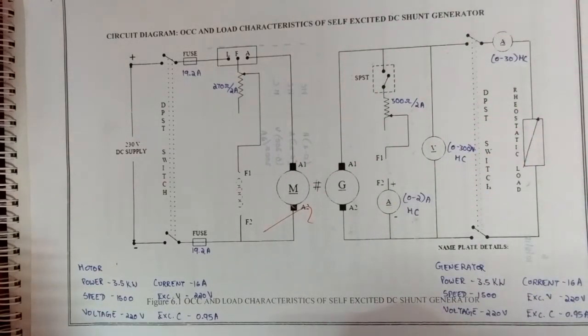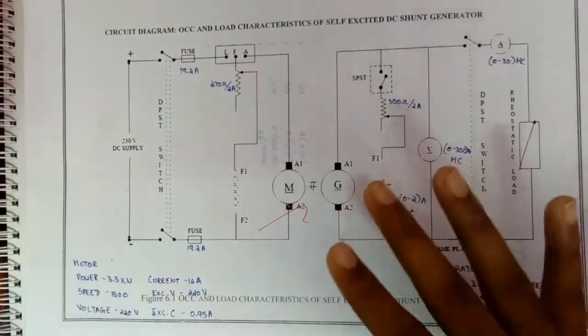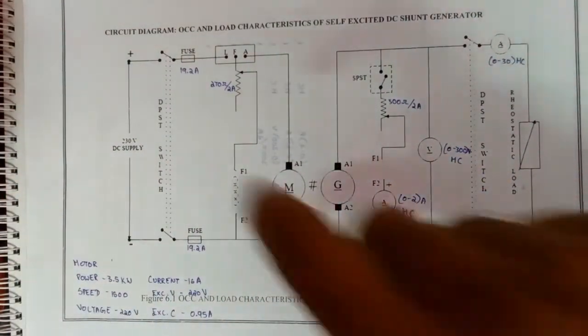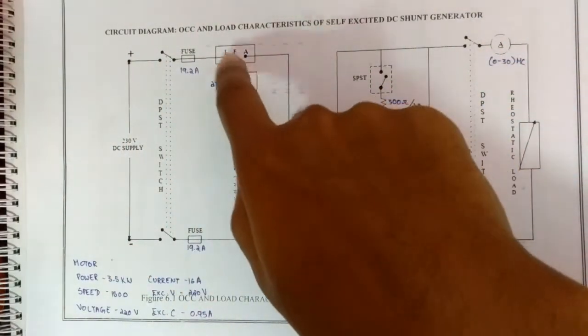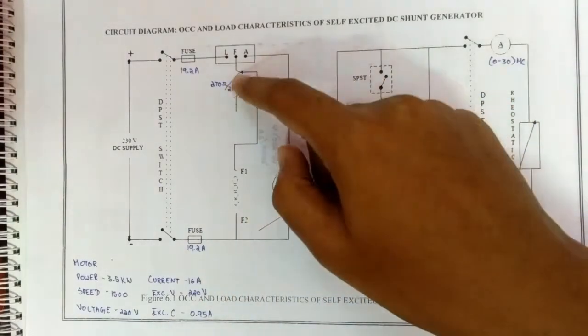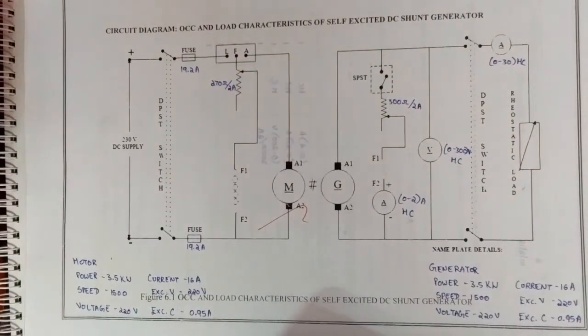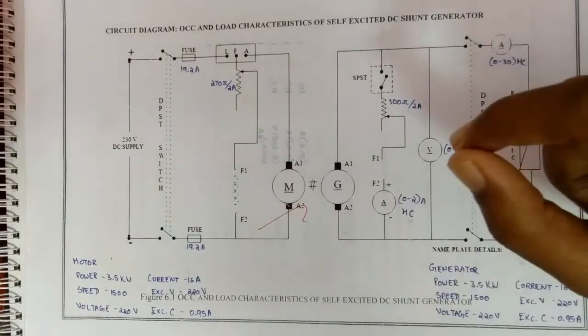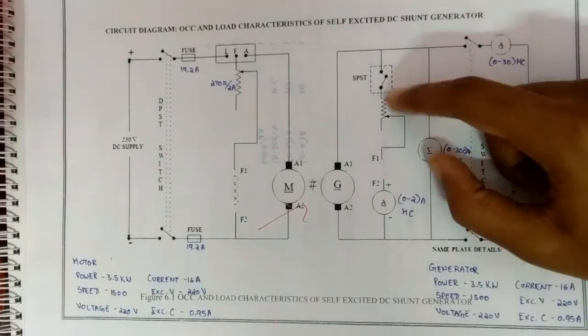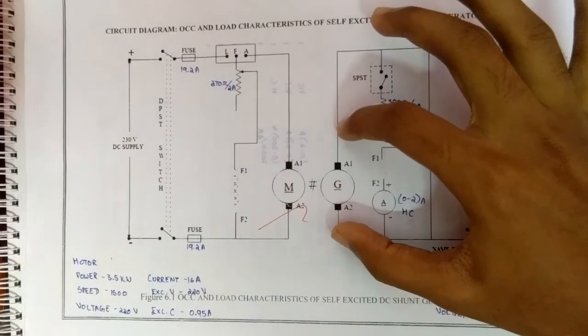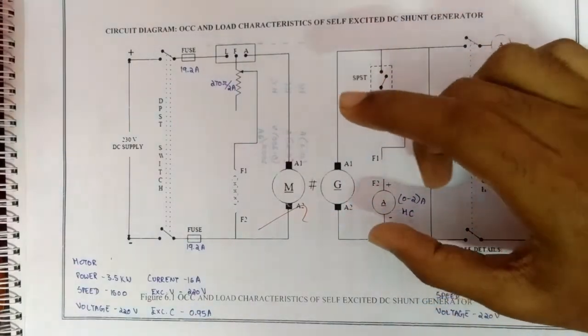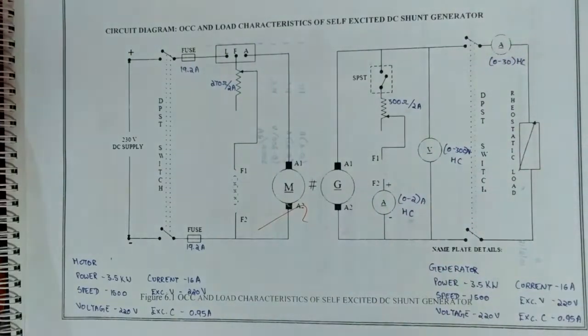The procedure for the OCC test is: first, the connection should be made as per the circuit diagram. By closing the DPST switch 1 and using the 3-point starter, the motor is started. The motor field rheostat is adjusted and the rated speed is set. The residual voltage is noted down from the voltmeter. Finally, the generator field rheostat is varied and generated voltage EG and corresponding field current IF are noted down. The same procedure is repeated up to the rated voltage.